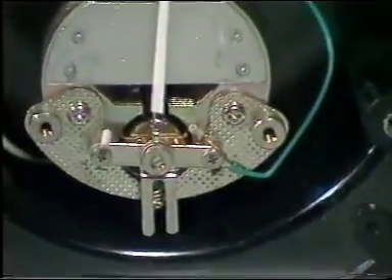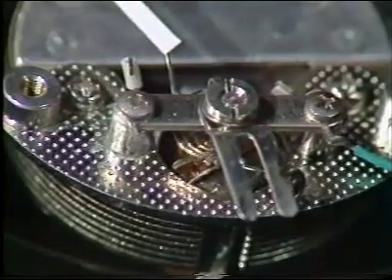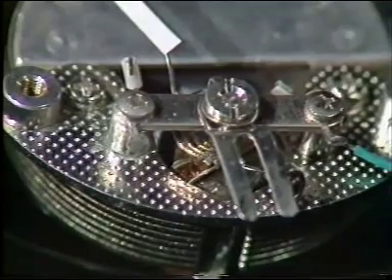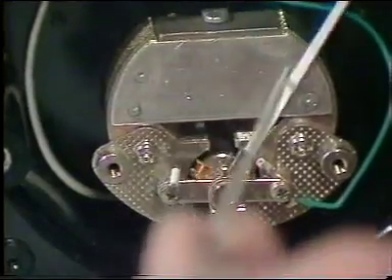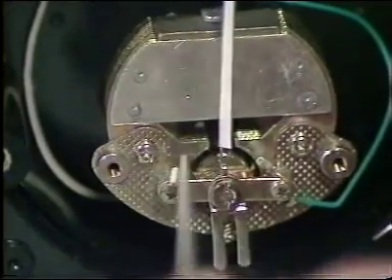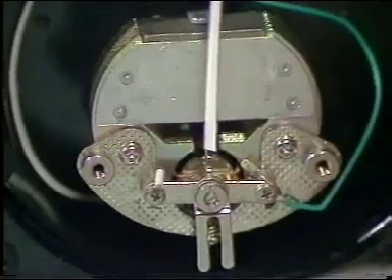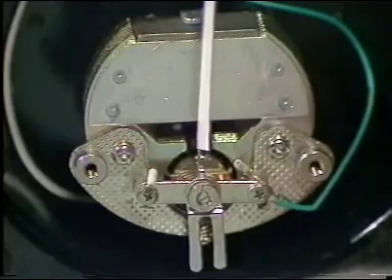There's one other thing I'd like you to look at, if you can see it. It's a tiny coil spring at the front here. That spring is there to ensure that the pointer reaches a particular deflection corresponding to a current. The force on the current is constant, independent of the deflection, but the force of the spring increases as the deflection increases, so that the pointer comes to rest at a point at which the force on the current is exactly balanced by the force produced by the spring.